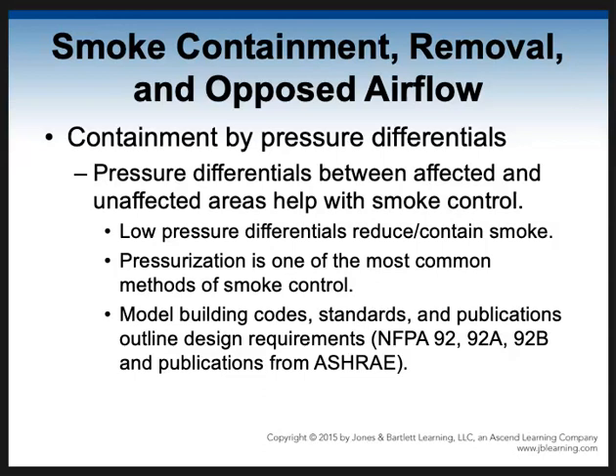So again, they use pressure differentials to contain the smoke in certain areas or keep it out. So if you pressurize a hallway by having fans above pushing air in, when somebody opens the door, they're going to feel a blast of air, and the smoke is going to be pushed out. They will be able to go in. The door will be forced closed behind them, but the smoke won't come in with them. So pressurization is one of the most common methods of smoke control, especially in high-rise buildings and our larger buildings.